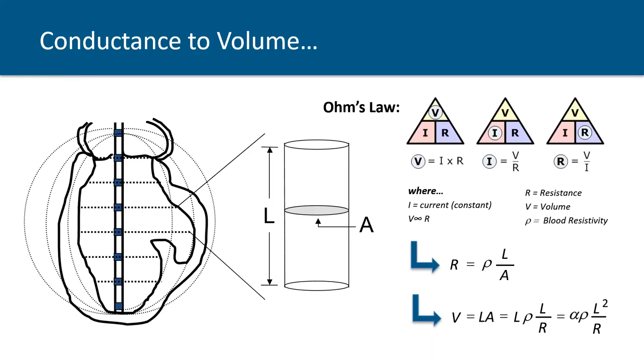You can see that volume here is proportional to the resistivity of that material, times the distance between those electrodes squared, divided by the resistance. Hence the name conductance catheter, because volume is proportional to 1 over resistance, which is essentially conductance. For historic purposes, this equation was derived by Jan Nijboer back in the 50s. I know it's attributed to Jan Baan in the 80s, but if you look at their initial papers, they actually reference some of the early work of Nijboer as late as 1959. So we have a relationship between volume and conductance.